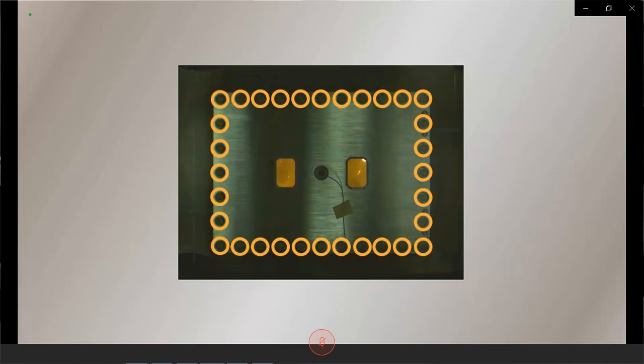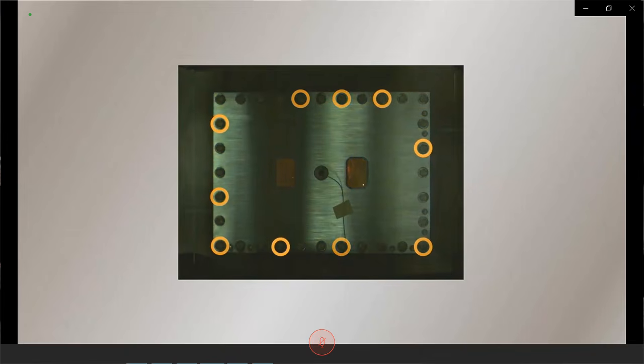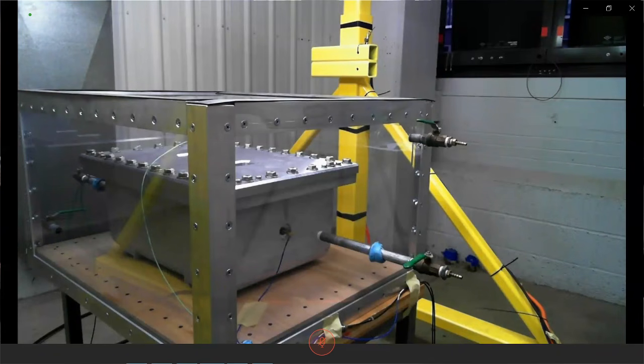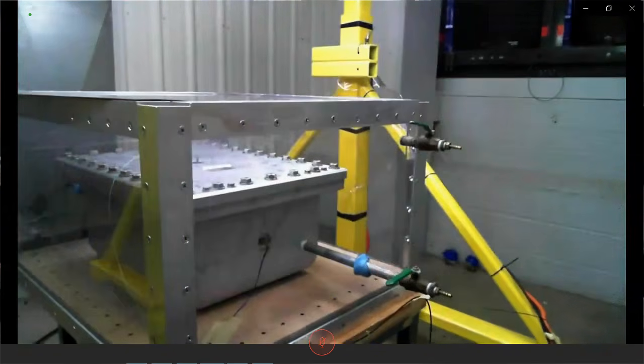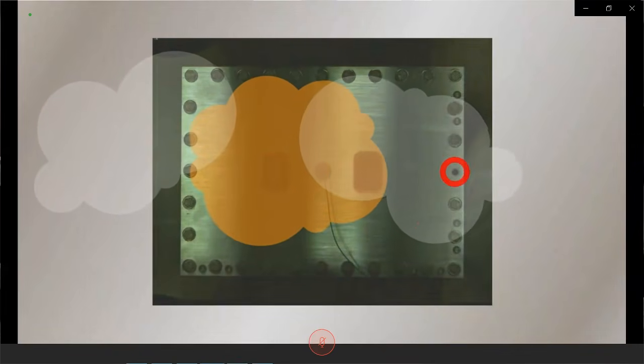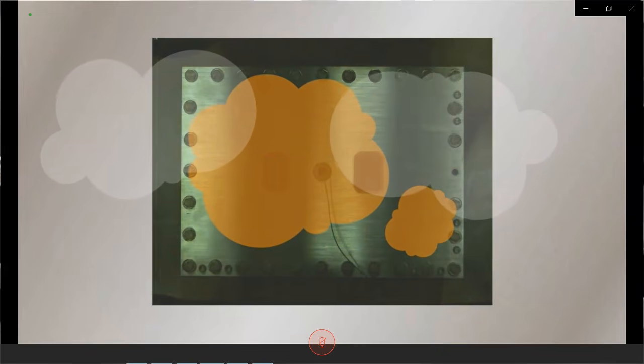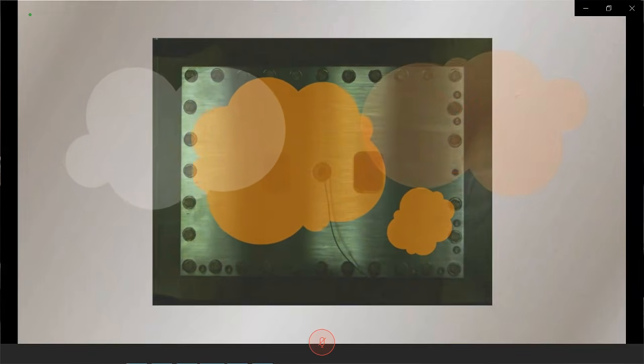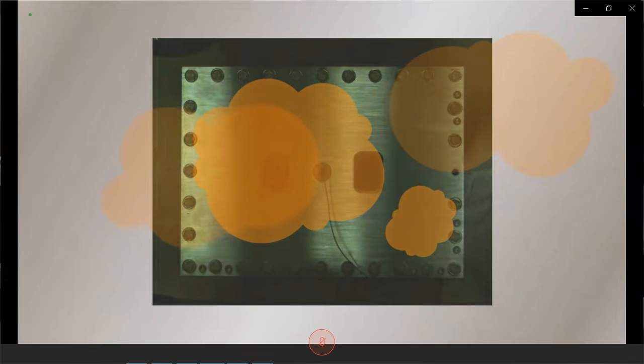However, instead of properly securing all enclosure bolts, some installers believe that randomly installing and tightening just a few of them is good enough. But watch what happens when this seemingly minor step is skipped. For this test, we secured all cover bolts except one. As you can see, when a spark ignites the hazardous gases inside the enclosure, this one missing bolt allowed the burning gases to escape before being properly cooled. The result? The hazardous gases outside the enclosure are also ignited, causing a significant secondary explosion, which can lead to equipment damage and injury or death to personnel. Watch in slow motion what can happen in a flash.